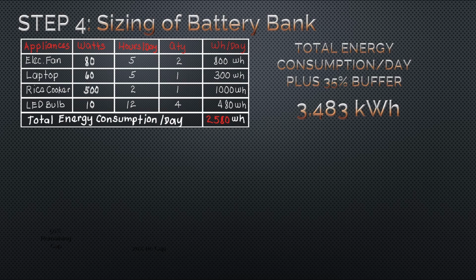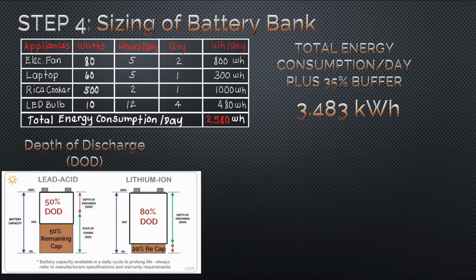Now, will those parameters be enough to compute the size of the battery bank? The answer is no, because there is another parameter to be considered, and that is the DOD or depth of discharge of the battery. This parameter is recommended by the manufacturers of the battery, wherein the purpose is to lengthen the lifespan of the battery. Please note that the DOD for lead-acid battery is different from the DOD of lithium-ion battery. For instance, the lead-acid battery has 50% DOD, while lithium-ion battery has 80% DOD.